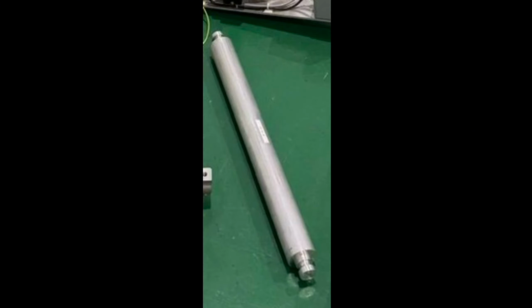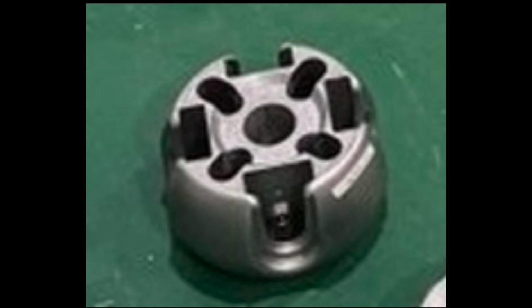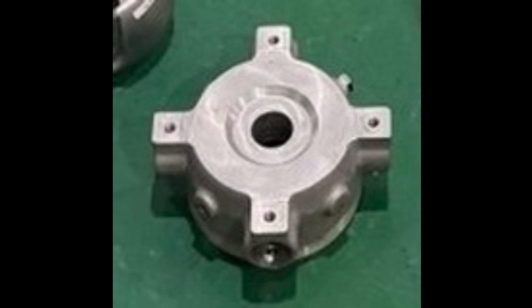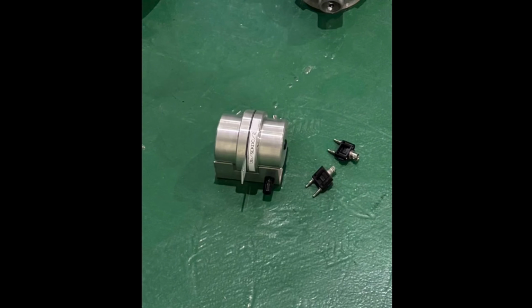The next component we have is the connecting rod. The connecting rod acts as a conductive connection element and is made of aluminium. The next component is the connecting cup and floor pedestal. These two components will act as a conductive connection element. The next component is called SEK-AC, a secondary unit for the AC divider which incorporates the LV capacitor. It is connected between the HF socket of the measuring capacitor and the picoscope.